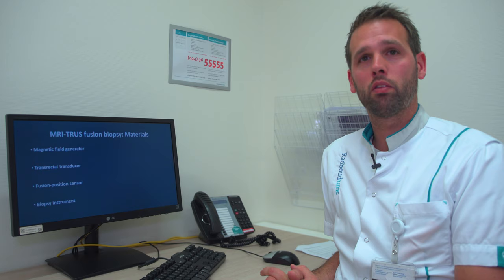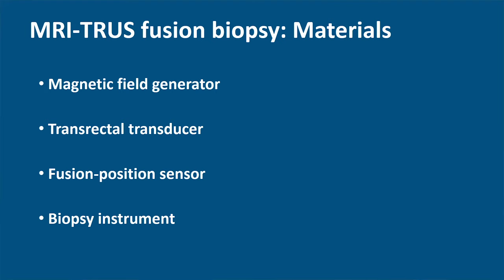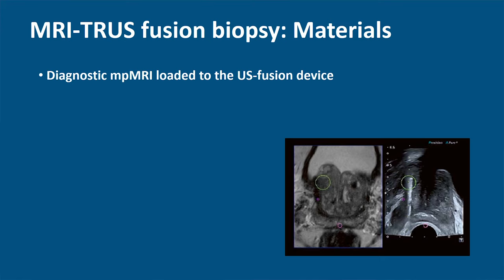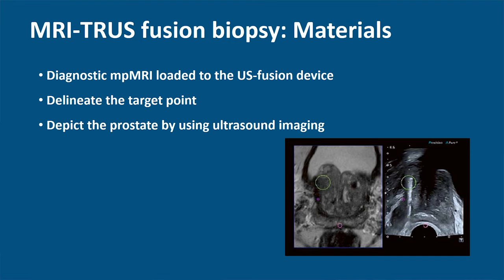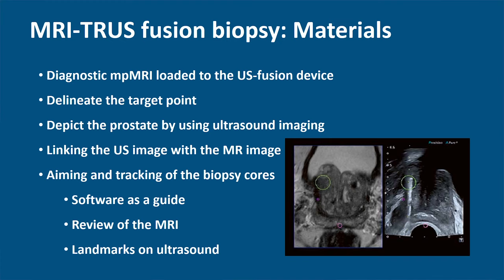The MRI-TRUS fusion setup usually consists of a magnetic field generator, a transrectal transducer, a fusion position sensor, and a biopsy instrument. The MRI-TRUS fusion biopsy procedure consists of the following steps. The first step is to upload the multiparametric MRI into the ultrasound device. The second step is to delineate the target point, which can be done by the radiologist up front; otherwise you have to do it yourself. The next step is to detect the prostate using ultrasound imaging, followed by linking the ultrasound imaging with the multiparametric MRI imaging. The next step is aiming and tracking of the biopsy cores.